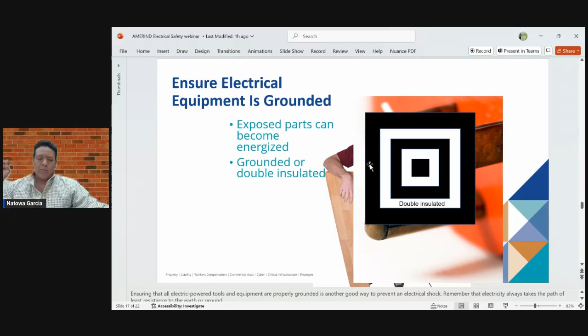The purpose of grounding is to provide a safe path for electricity to travel to the ground. If the grounding path is broken, for instance by not having a ground prong on the plug, electricity will take the path of least resistance, which may be through your body. Electric power tools and equipment must be grounded or double insulated. Double insulated tools do not have to be grounded because they're designed not to have electrical hazards, as long as their insulation has not been damaged. This kind of tool will be marked with the symbol of a square within a square, double insulated. Take a look.